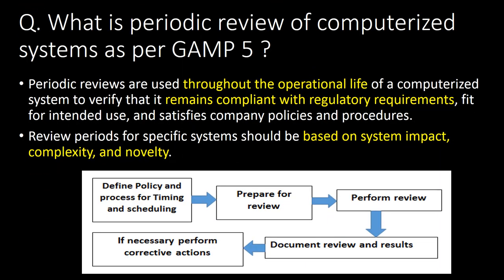What is periodic review of computerized systems as per GAMP-5? Periodic reviews are used throughout the operational life of computerized systems to verify that the system remains compliant with regulatory requirements, fit for intended use, and satisfies company policy and procedures. Review periods for specific systems should be based on system impact, complexity, and novelty. The periodic review procedure includes defining policy and process for timing and scheduling, preparing for review, performing the review, documenting the review and results, and taking necessary corrective actions if required.